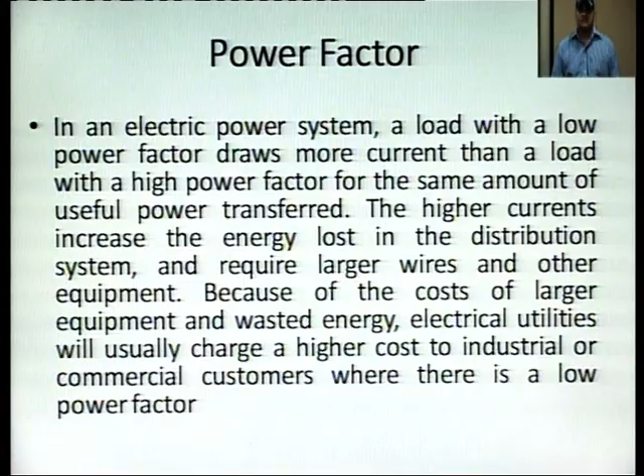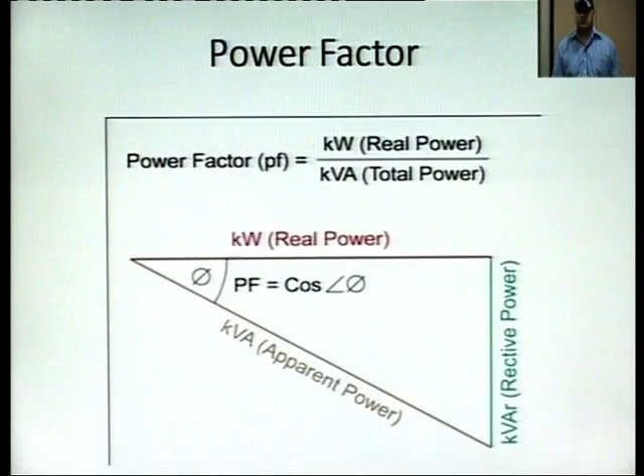So what is the power factor? Power factor is kilowatt, the real power, divided by kVA, the total power. In this graph, kilowatt is the real power and kVA is the apparent power, and the green one shows kVAR, the reactive power. There is an angle phi, and the cosine of this phi is called the power factor, the cosine of the angle between the real power and apparent power. The reactive power is what is stored in the equipment.